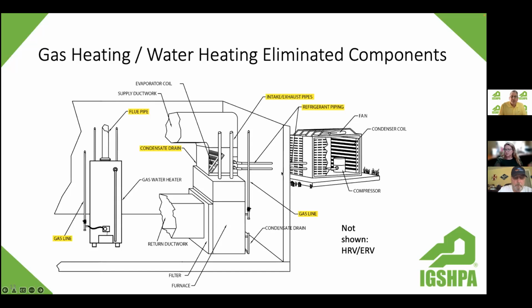If we go with a packaged geothermal unit, we don't need this line set. There's cost, wall penetration that needs to be considered. We still need a condensate drain for cooling mode, but we don't need two. I have one here for the gas furnace because it's a condensing gas furnace, and I have a second one for the evaporator coil. So when we start to look at the components, what do we actually take away when we go with geothermal? It's awfully nice not to have all that gas piping and refrigerant line piping and venting. There's a cost associated with that, both from a component standpoint and from a labor standpoint.